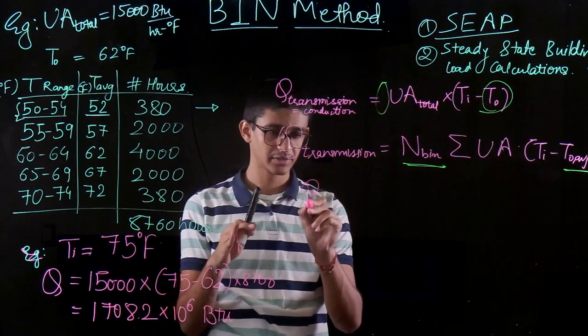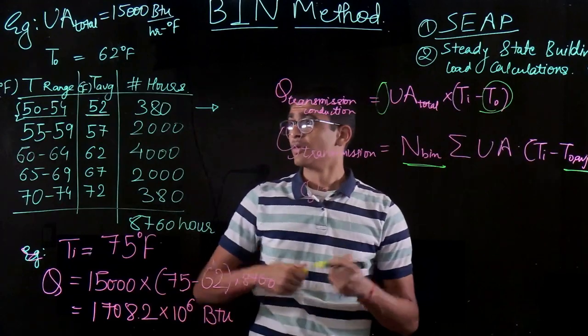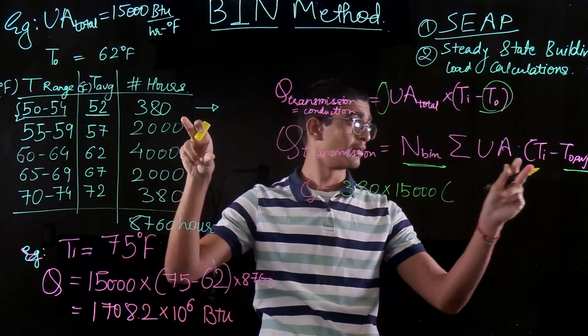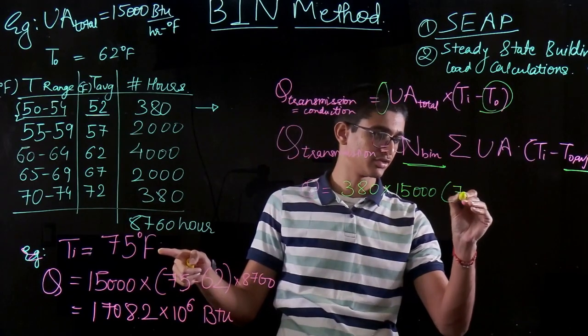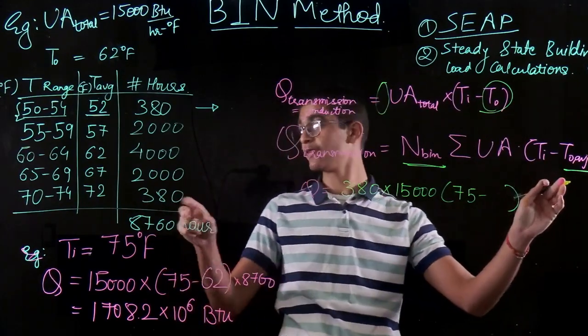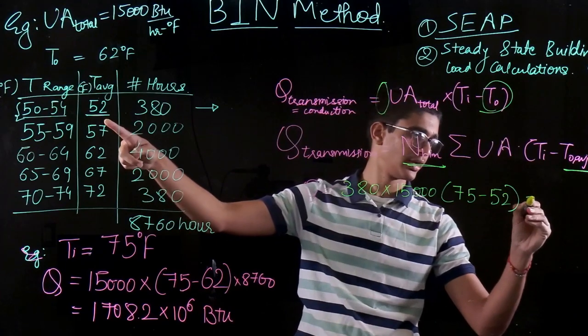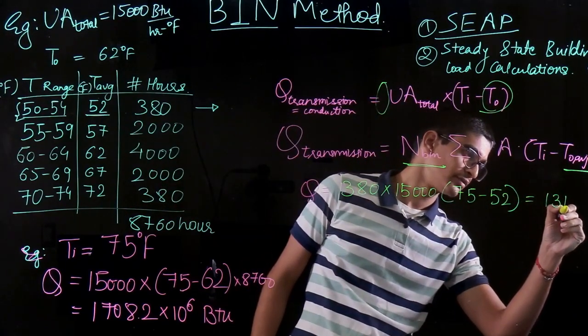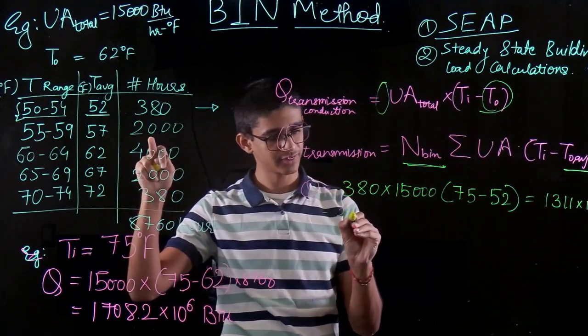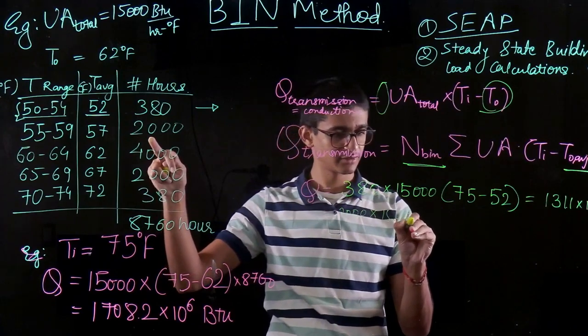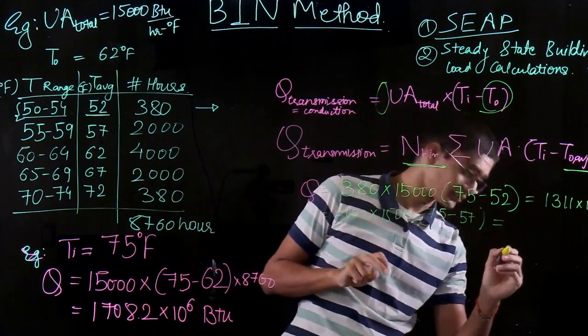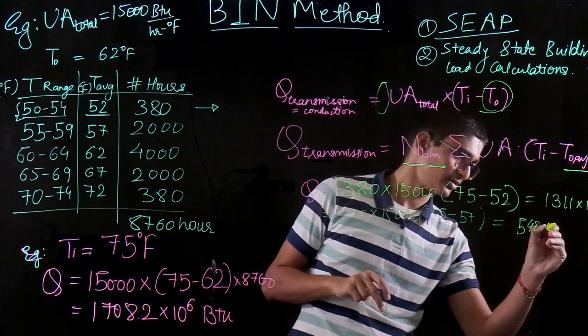Now using the BIN method: for the first bin, Q = 380 hours × 15,000 BTU/(hr·°F) × (75 − 52) = 1,313.0 × 10⁶ BTU. Wait — that comes out to 131.1 × 10⁶ BTU. For the next bin: Q = 2,000 × 15,000 × (75 − 57) = 540.0 × 10⁶ BTU.